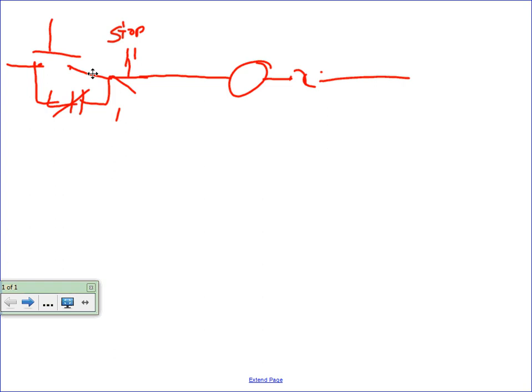So what we normally use is an auxiliary contact off the disconnect to also disconnect the control power when we disconnect the main power to that product. And then control power transformers. So I just want to cover the basics on starters. You've got different types of control, two-wire, three-wire. You've got different types of control power: separate, common, or CPTs.